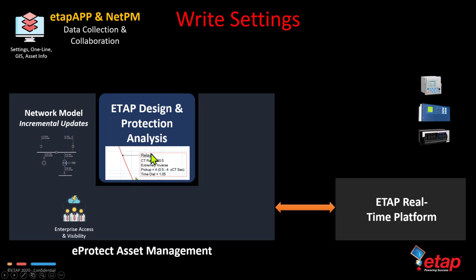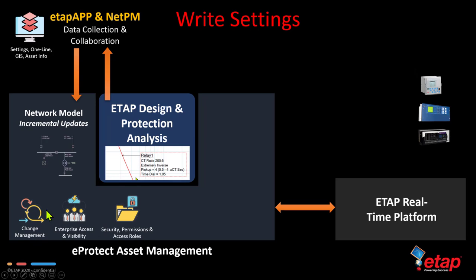However, ETAP knows that this relay 1 is a particular type of relay. So essentially by making this change, ETAP automatically generates the settings, sends it over NetPM, which then downloads it into the eProtect database. And that settings file is essentially visible across the enterprise. That triggers a change management workflow that goes through the security permissions and access roles of who can essentially further process those settings. A schedule setting retrieval and audit is essentially run, which is comparing the existing setting inside the eProtect database with the new settings that are coming in.